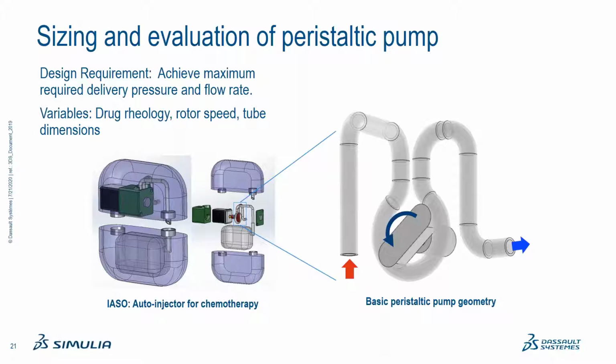The peristaltic pump is a simple device favored for the fact that no moving parts come into contact with the drug, but its performance is difficult to characterize with accuracy without the use of advanced simulation methods. In this case, the performance of the pump must be known with reliable accuracy because it is at once a pump and a dose measuring device.